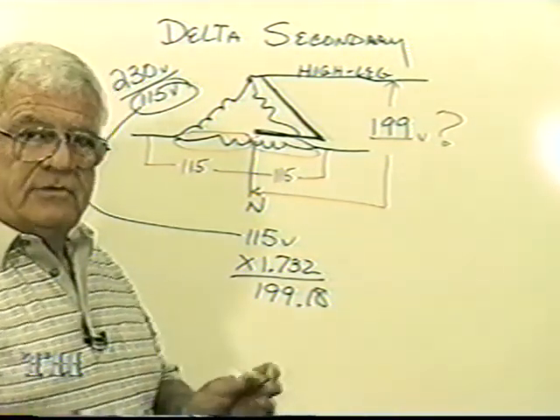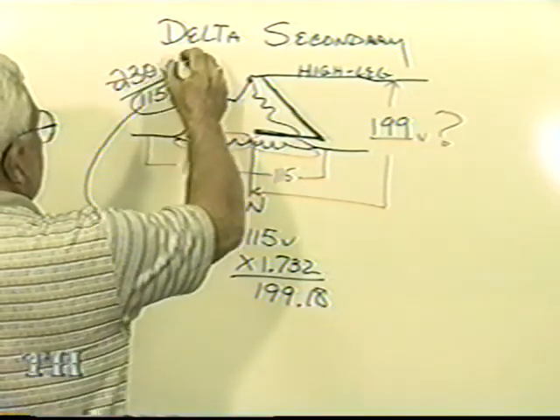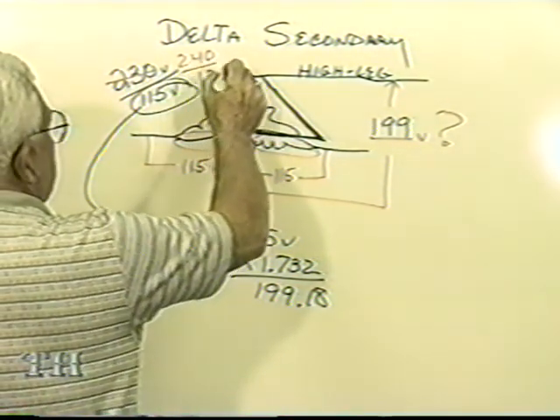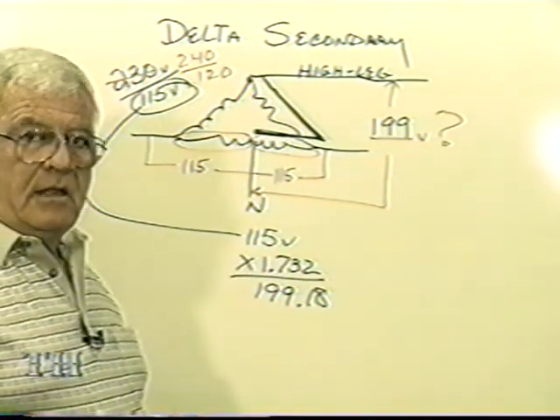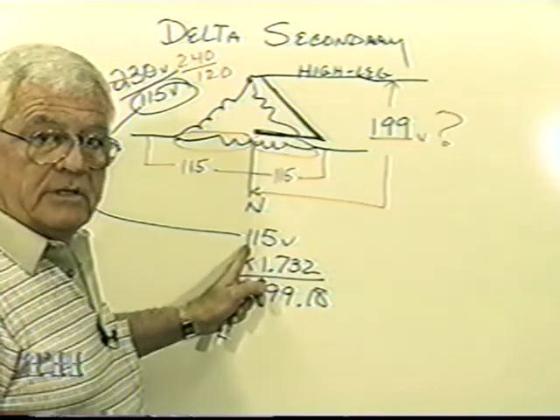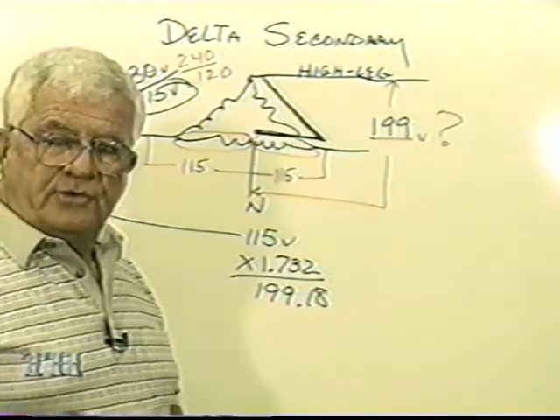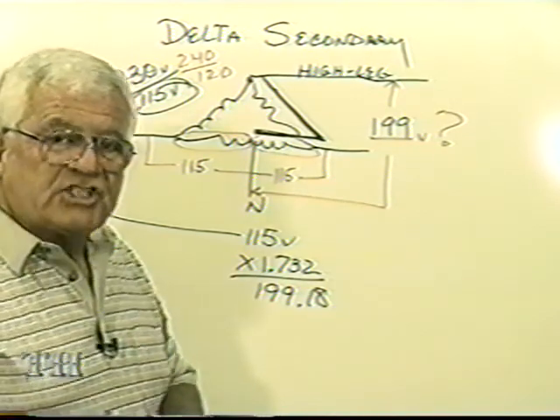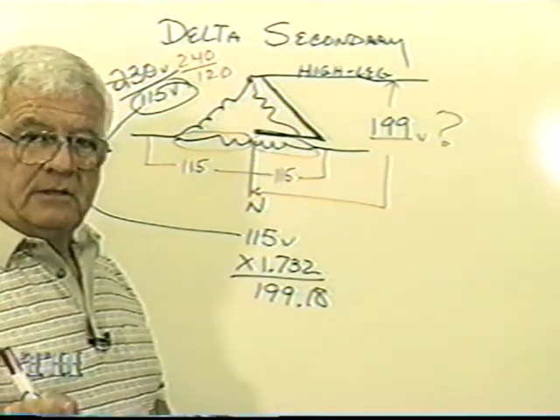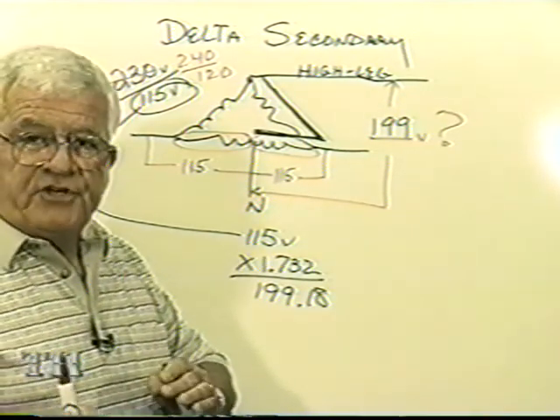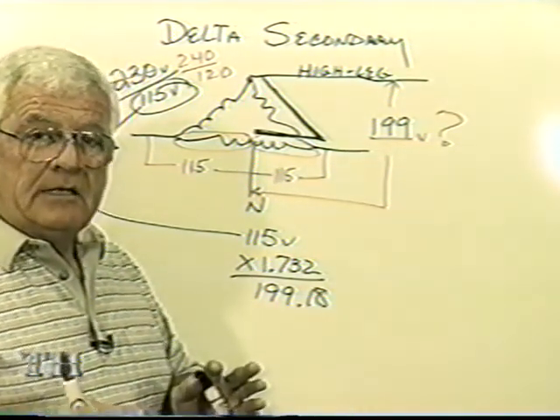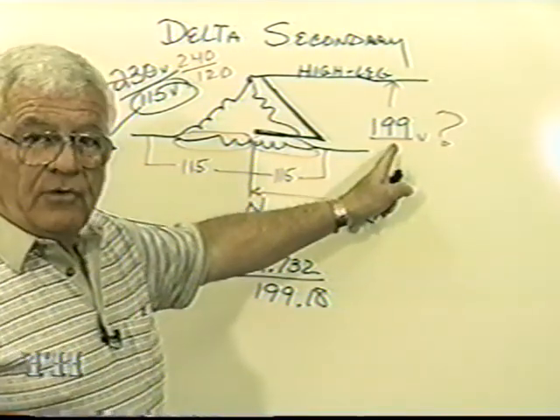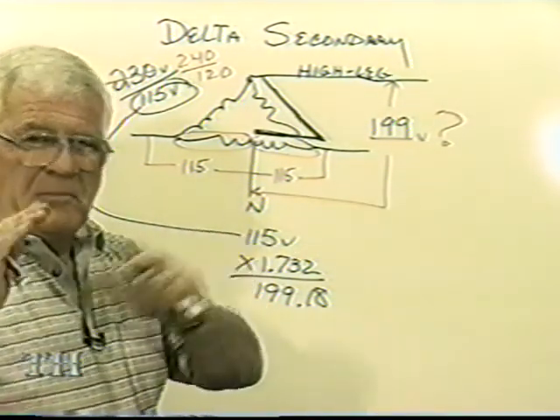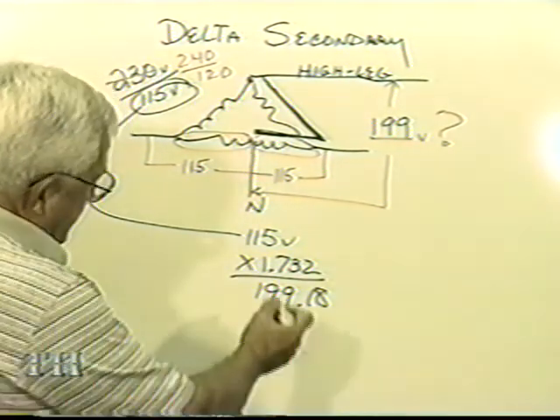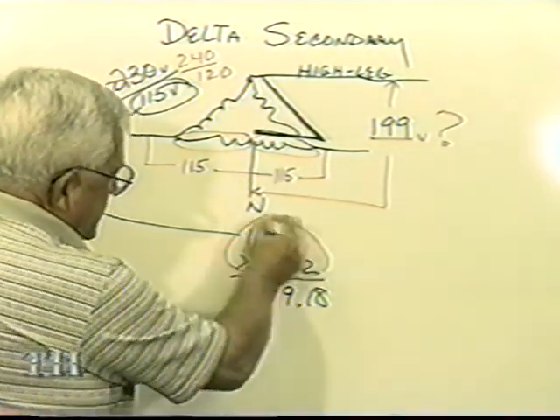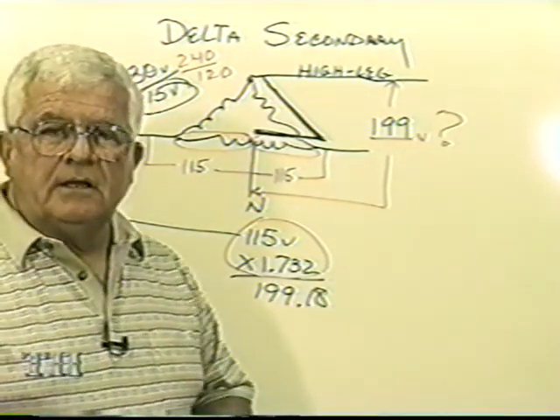And see, the reason they do this, if this was 240, 120 - if you took 120, your lower voltage, times the square root of 3, there's your 208 volts. So sometimes, intentionally, they don't make it 120, 240. They'll make it 230, 115, or 220, 110, because when you change voltages, this voltage changes. So there is no memorizing 208. What you memorize is the lower voltage times the square root of 3. Then you'll be okay.